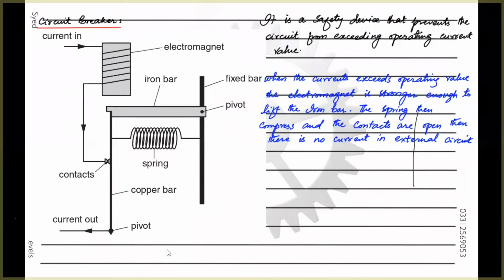The current is high, when the current through the live wire is greater than the operating current value. If the appliance is of 8 amperes, the operating current value is 8 amperes, and the circuit breaker rating should be slightly greater, it can be a 10 ampere circuit breaker.